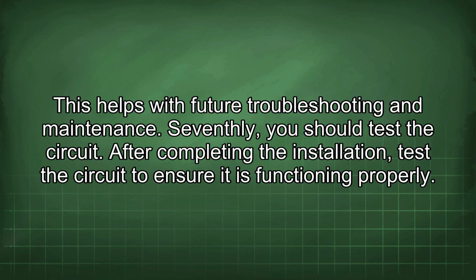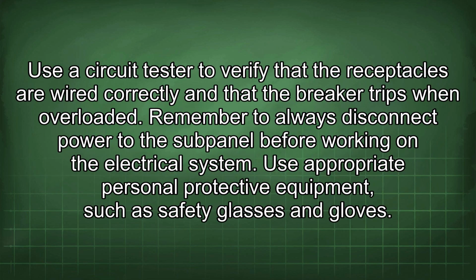Seventhly, you should test the circuit. After completing the installation, test the circuit to ensure it is functioning properly. Use a circuit tester to verify that the receptacles are wired correctly and that the breaker trips when overloaded.